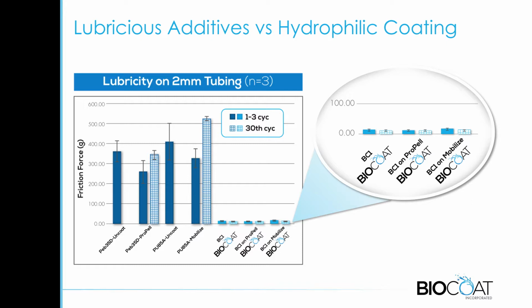So let's look at some additives and then finally some evaluations of hydrophilic coatings. The first part is some lubricious additives that can be added to the extrusion to minimize friction. This is an example of data that we generated with completely unmodified polyurethane and PEBAX tubing, as well as ones that have low friction additives added into the extrusion, and then putting a hydrophilic coating on top of them. Taking a look at all of these on these 2mm tubings, you can see that both of these additives do reduce the friction somewhat from the unmodified ones, by around 25%.